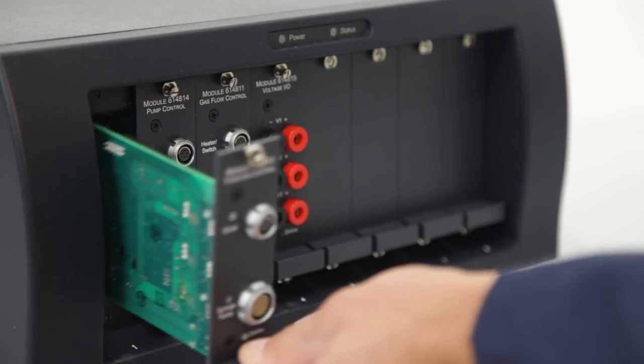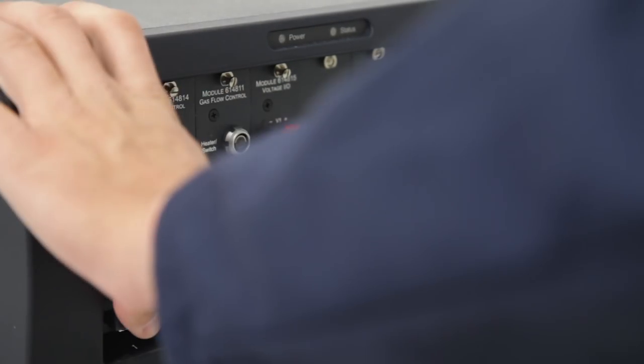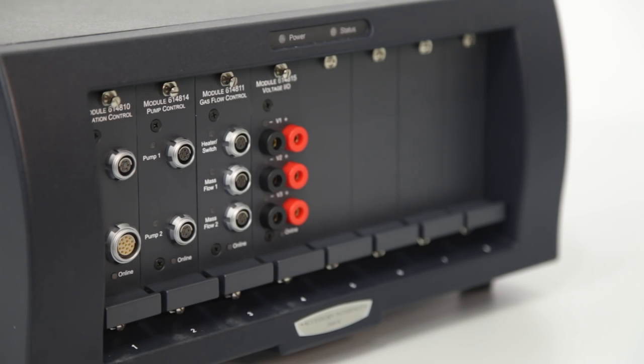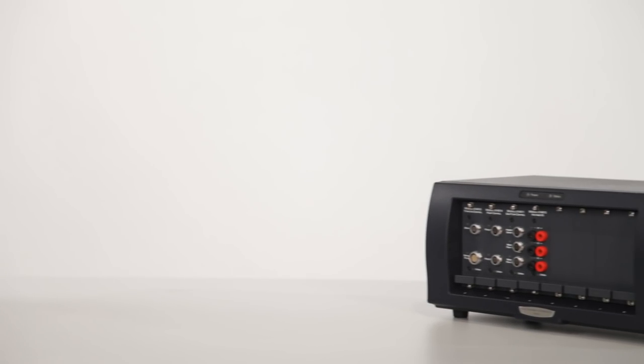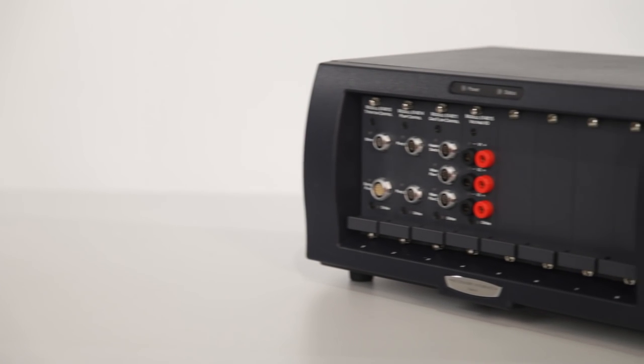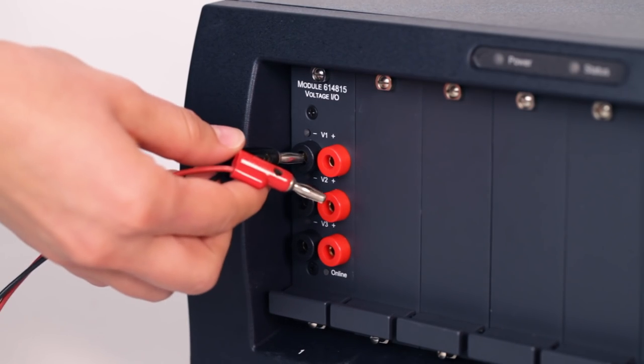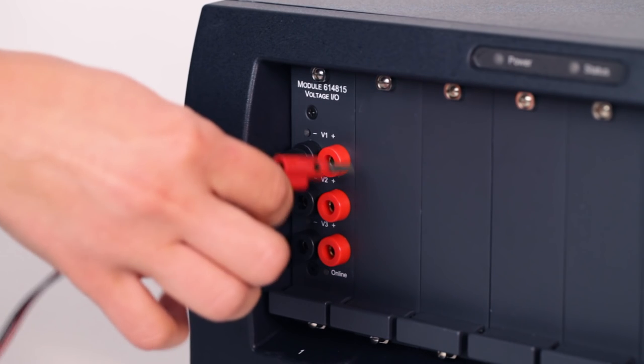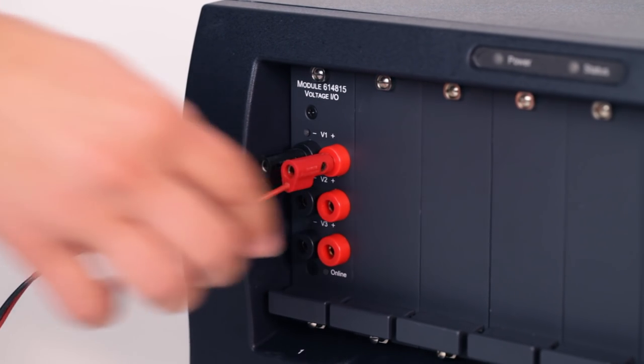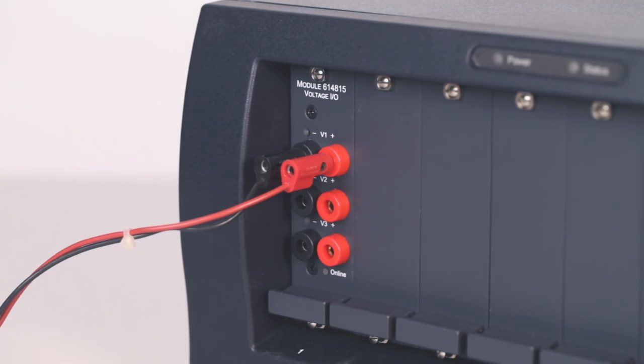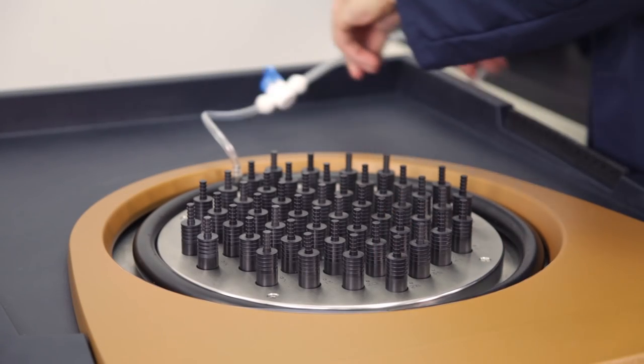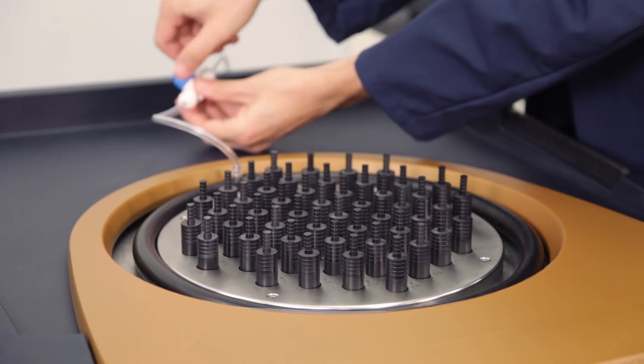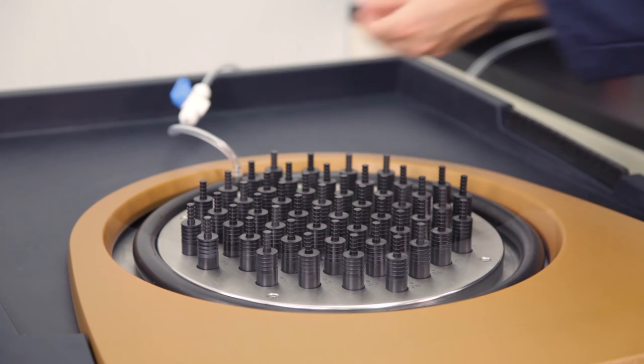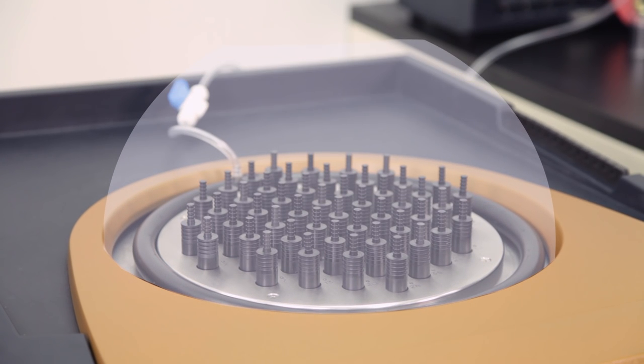The TAM IV can be equipped with many different accessories to allow interactions with samples during tests and test control. The new accessory interface has the capacity to house up to 8 modules at a time, including the voltage I/O module, interfacing up to 3 independent probes or sources, such as the pH probe and light source. For operation at sub-ambient temperatures, the dry gas purge ring creates a dry air dome above the calorimeters to prevent condensation in sub-ambient measurements, now achievable on the TAM IV.